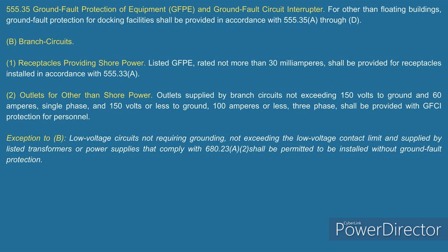And it says outlets supplied by branch circuits not exceeding 150 volts to ground and 60 ampere single phase, and 150 volts or less to ground, 100 amperes or less, three phase, shall be provided with GFCI protection for personnel. Okay. Now, that is where you're going to be setting up, just like I do for shore power. These are going to be cord and plug connected type devices. Right. Okay. This is not going to be something that's hardwired. And that's where the problem starts coming in.